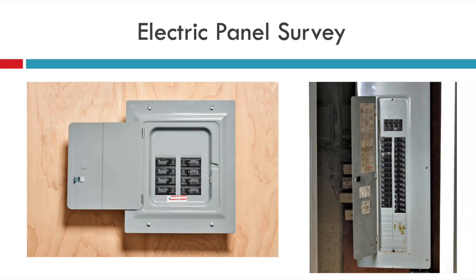Unfortunately, that's going to leave no room for improvements with other circuits. So if I wanted to add another electrical circuit for a new appliance, I wouldn't be able to once that heat pump is installed. A lot of times you can just take a quick look at the panel, and the physical size may lead you to how big that service actually is. There's a great picture on the left-hand side of a 60-amp service — you can get them very small on small ranch houses, trailers, or condos. A lot of times it's not feasible to do an upgrade on a service this small in a condo building because you can't upgrade all the condos without upgrading the wire going to them and the main service coming to those buildings. But on single-family homes, you could make that upgrade and it's still cost-effective. The picture on the right is of a normal 100-amp panel.